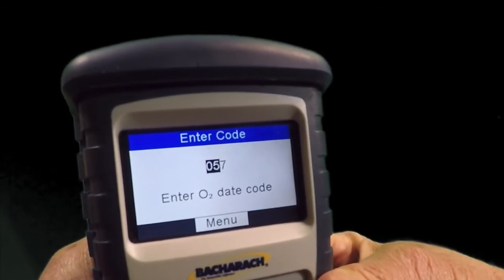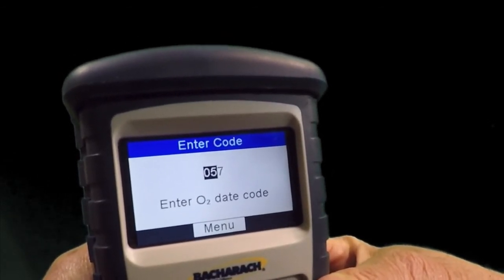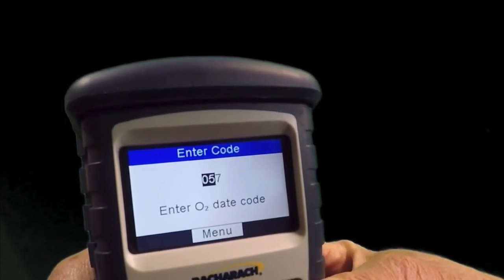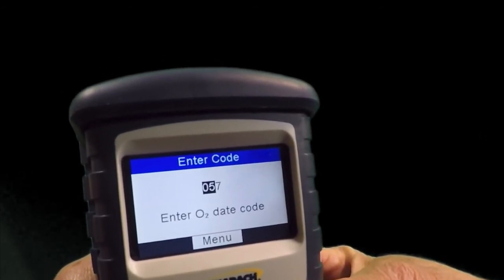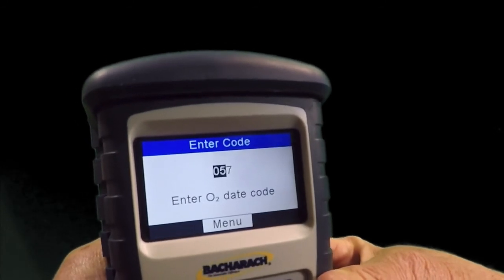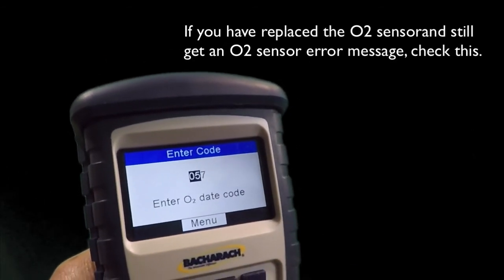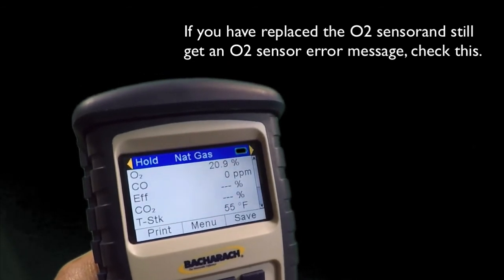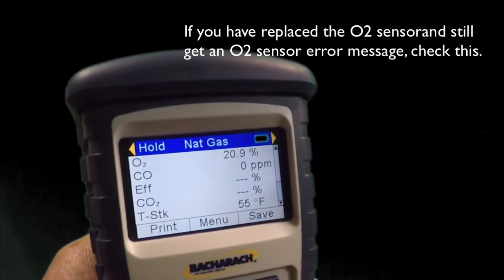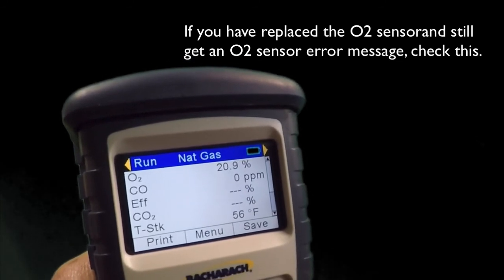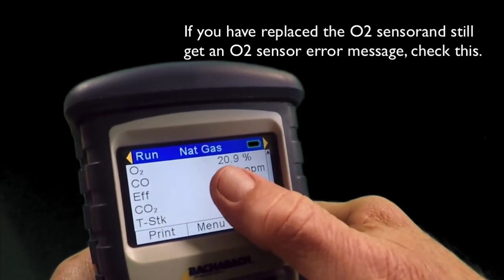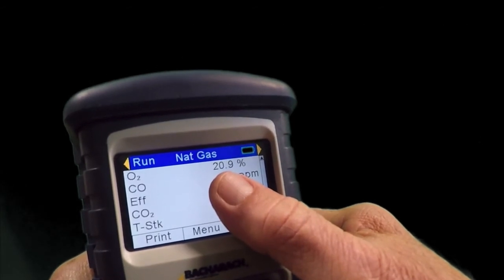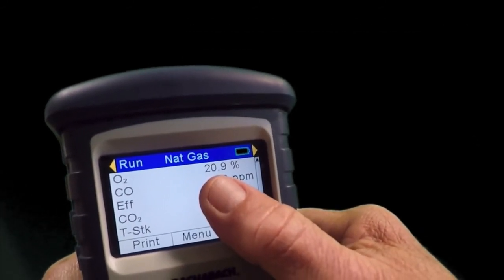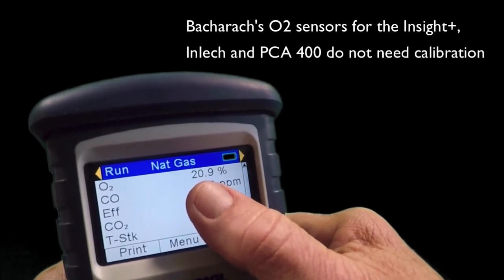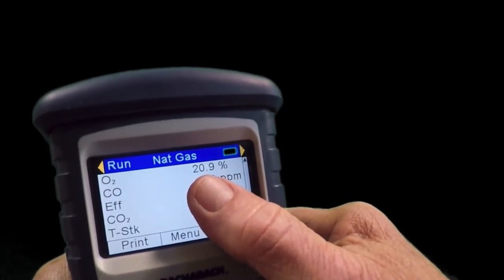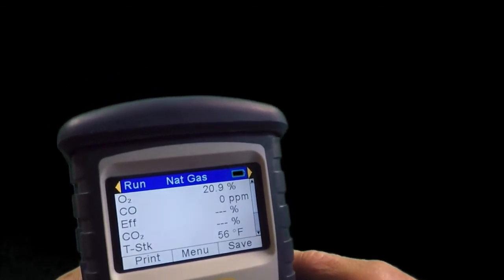When you install a new sensor, it's absolutely critical that you go in and change this date code to match the date code that's on the side of the sensor. Otherwise, it's going to keep coming up with an O2 sensor error. One real easy way to tell is if you have an oxygen sensor error and you go to the main screen, the run hold screen, hit run. If it says 20.9% oxygen in the display, that means the sensor is working just fine. Likely it's the date code that hasn't been reset yet. So keep that in mind.